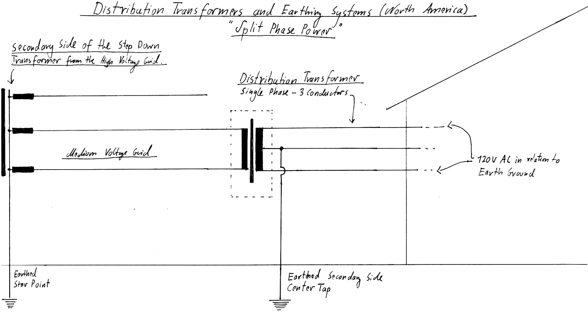First of all, the medium voltage grid is usually realized in a star point configuration rather than in a delta. My guess would be that this is done because the distribution transformers are not three-phase transformers at all, but are connected with a single primary winding between two phases of the medium voltage grid, representing an unsymmetrical load.